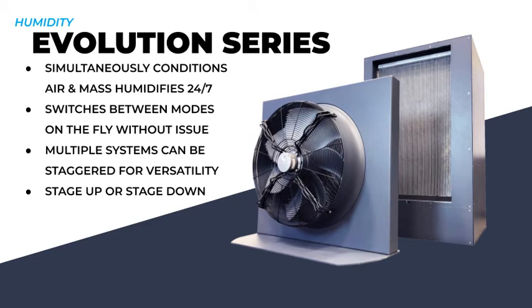We can stagger systems, so that, for example, if there are multiple systems in a room, 3 of the systems can be designated with one set point, while the 4th system can have a different set point. We can stage up, we can stage down, there's a lot more versatility, and with that dialed in, it doesn't matter what else is happening, whether your insulation isn't strong on a warm day or the temperature is slowly increasing from the emanating heat coming in, because our Evolution series system is going to run. You can rest assured that it is mass dehumidifying while in air conditioning mode, because that's just what needs to happen. Then when it flips into dehumidification mode, that's fine too. We're just simplifying that process.